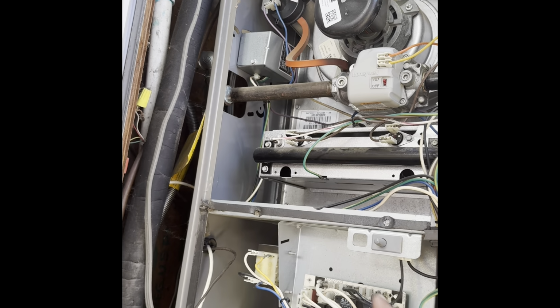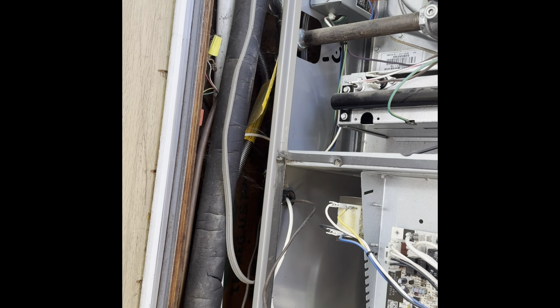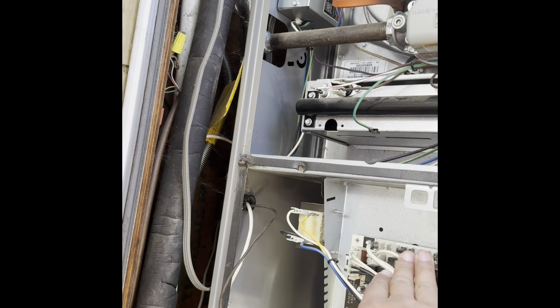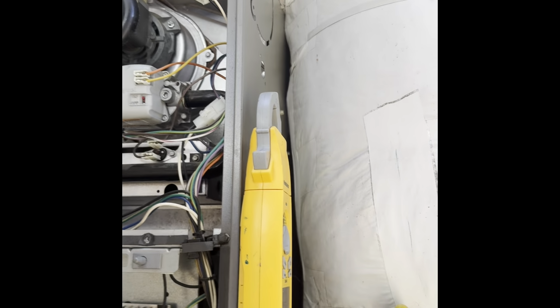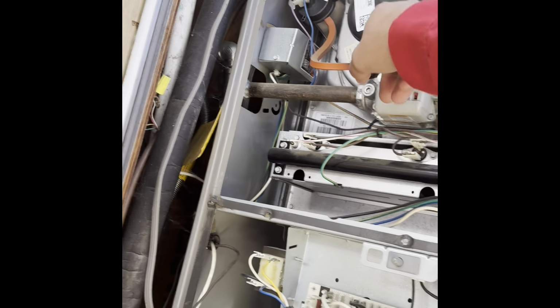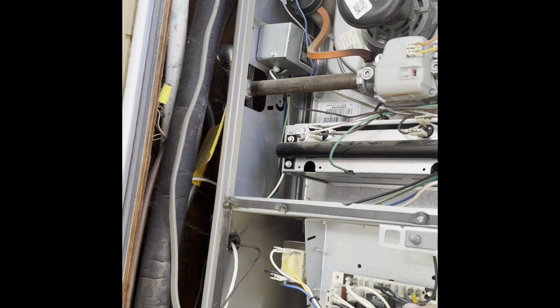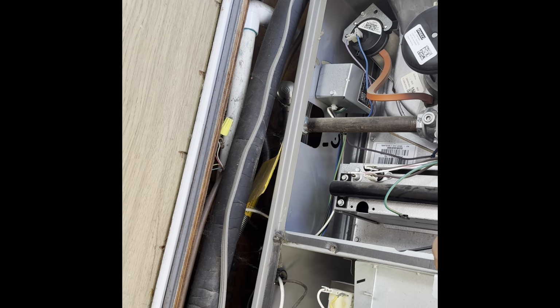Okay, so this is the blower compartment, and this is the circuit board, the control board that controls the whole system. It gets the signal from the thermostat. The board creates the sequence of operation by turning the inducer on and doing what it's supposed to do. The inducer comes on, creates negative pressure, closes these two connections, then sends a signal back to the board so it knows we have good exhaust. Then it turns on the igniter, a hot surface igniter in this case, and after it kicks in, the system turns on the gas and we have combustion. Oh, we have combustion, okay.